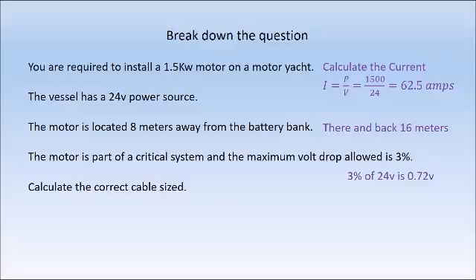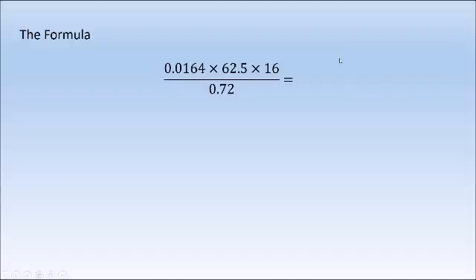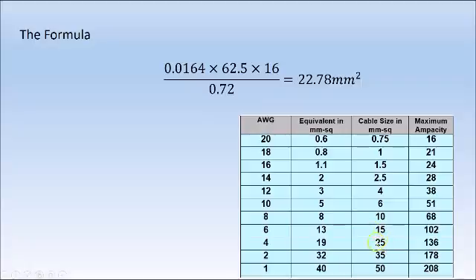Now we need to take that information and calculate the correct cable size. We input our data into the formula: 0.0164 times our current (62.5) times 16 meters (the length of our circuit), all divided by our maximum allowed volt drop. 3% of 24 volts is 0.72. That gives you a value of 22.78 millimeters squared — that's the smallest cable you could install to maintain that 3% volt drop. Cable manufacturers don't make odd sizes like this, so you round up to the next size. Looking at our cable chart, 25 millimeters squared is the next size up — that would be our cable size to maintain the 3% volt drop in this scenario.